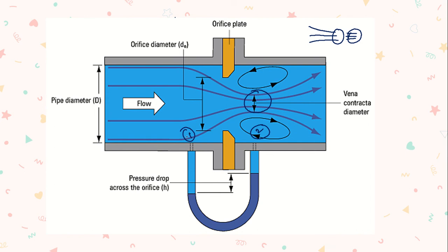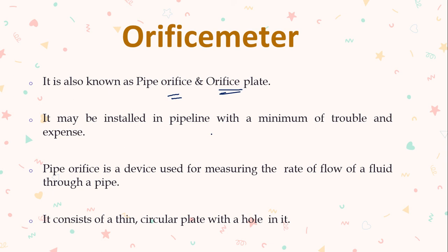One outlet of section one is connected to the pipe just before the orifice plate, and one outlet is connected to the manometer. One outlet of section two is connected at the vena contracta, and the second is connected to the second tapping of the U-tube manometer. The pressure difference is shown as a mercury level reading in the U-tube manometer. The orifice meter is also called an orifice plate or pipe orifice — it can be installed in any pipeline with less trouble, less expense, and less maintenance, and it calculates the rate of flow Q.